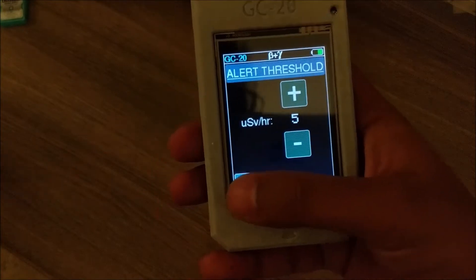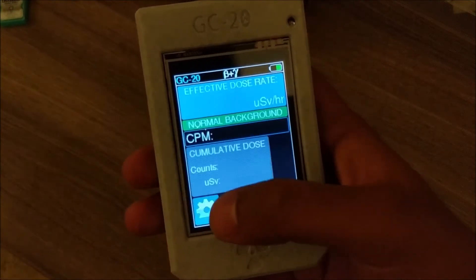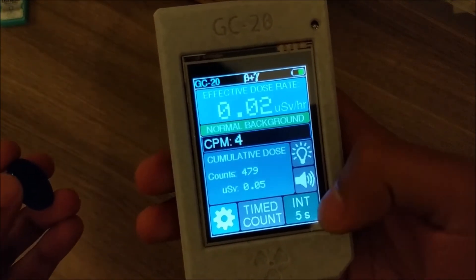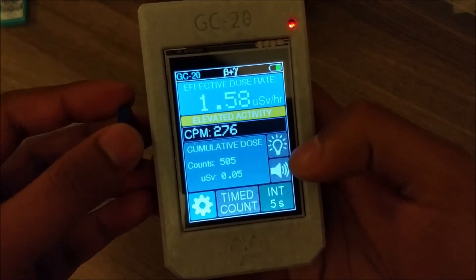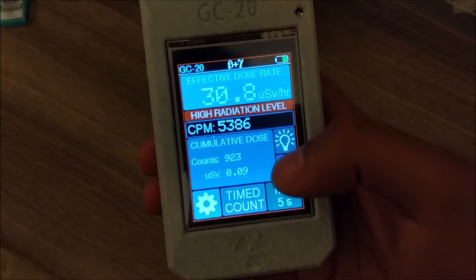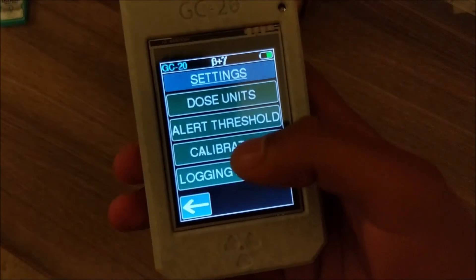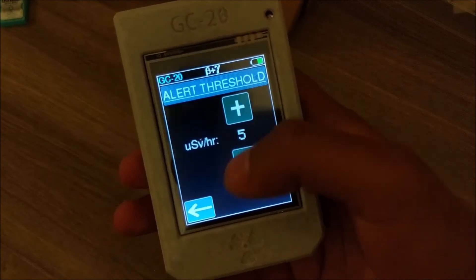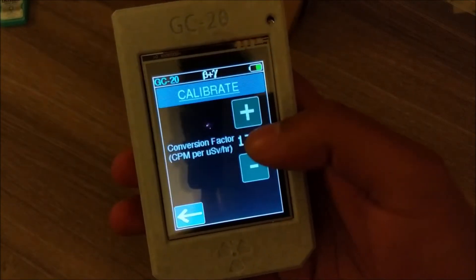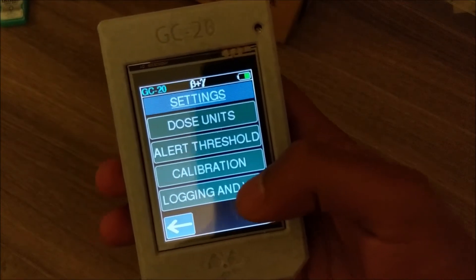Moving on to settings — it's a pretty simple settings menu. You can change your dose units and the alert threshold, which is the threshold at which the banner goes red. To demonstrate, it says 'high radiation level' — it's currently set at five, but you can change it to any number you want. You can also change the calibration.